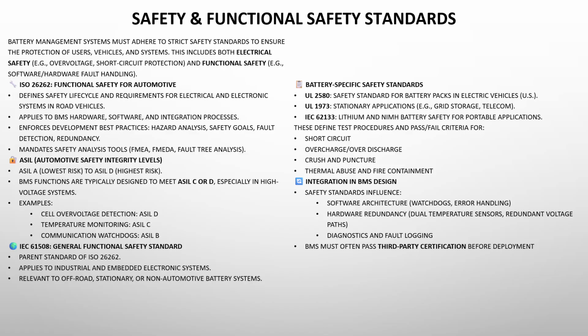They have to. So all these standards, functional safety like ISO 26262 and battery-specific safety like UL, completely shape how a BMS is designed. It dictates the software architecture needing watchdogs, robust error handling. It drives hardware choices, maybe needing dual temperature sensors for redundancy or separate pathways for measuring voltage. It requires comprehensive diagnostics and fault logging. Often a BMS and the battery system need third-party certification against these standards before they can be sold.